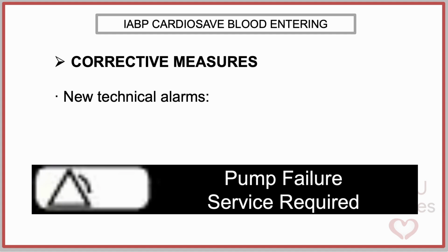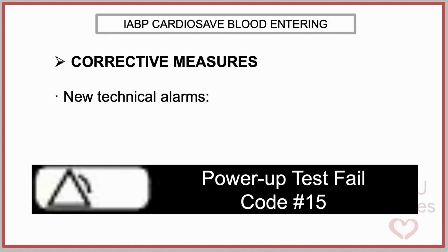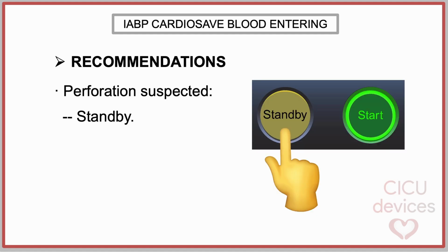a new technical alarm that reads, "Pump failure, service required," and another new technical alarm that reads, "Power up test fail code number 15 for consoles previously exposed to blood." These updates are intended to allow earlier identification of perforation and prevent resumption of therapy until the pump is serviced. The company also reminds users to follow the previously outlined recommendations in the event of suspected balloon perforation, which include the following.